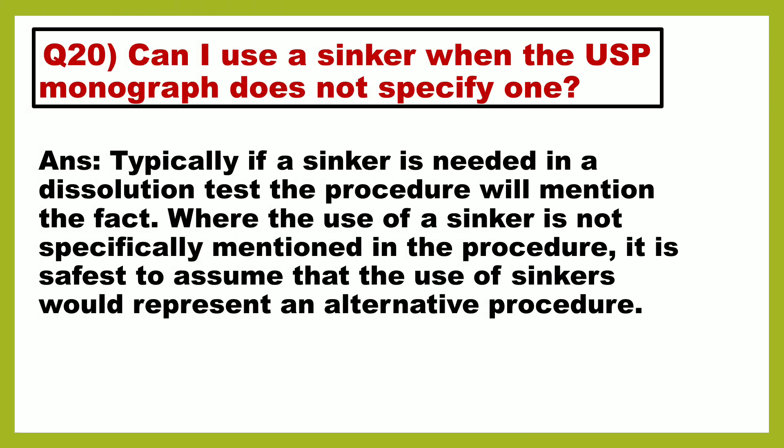And the last question is: can I use a sinker when the USP monograph does not specify one? Typically, if a sinker is needed in a dissolution test, the procedure will mention the fact. Where the use of a sinker is not specifically mentioned in the procedure, it is safest to assume that the use of a sinker would represent an alternative procedure.